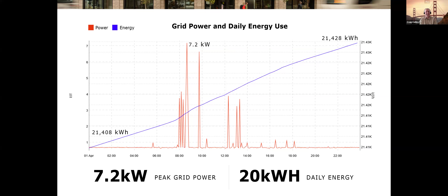So if you are in a situation where it may be advantageous to consider a UPS in lieu of a generator, there are some things to know. It does provide continuous power during outages, or if you have a microgrid, it can help to reduce concerns about people being stuck in an elevator momentarily during microgrid switching events. That's been a big benefit for us. You can determine a code compliant pathway for using a UPS for an elevator.